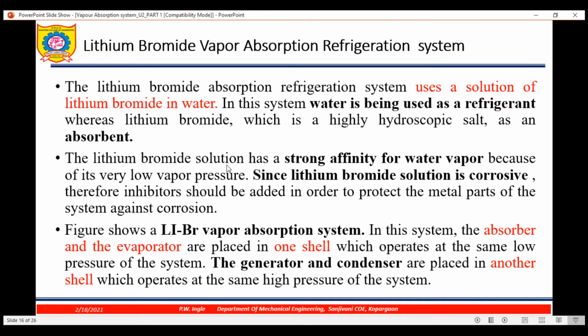Lithium bromide solution has a strong affinity for water vapor because of its very low vapor pressure. Since lithium bromide solution is corrosive, inhibitors should be added in order to protect the metal parts of the system against corrosion.